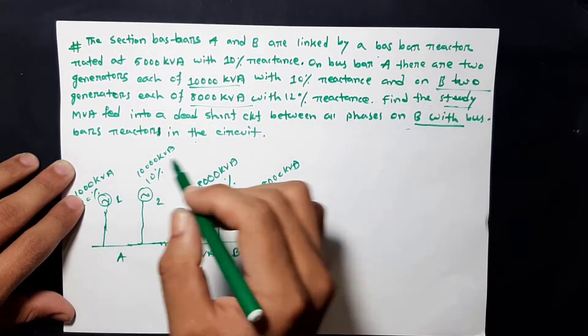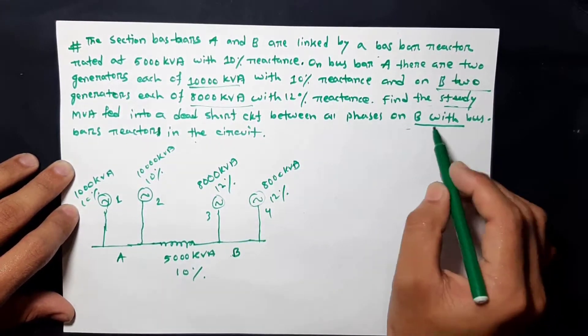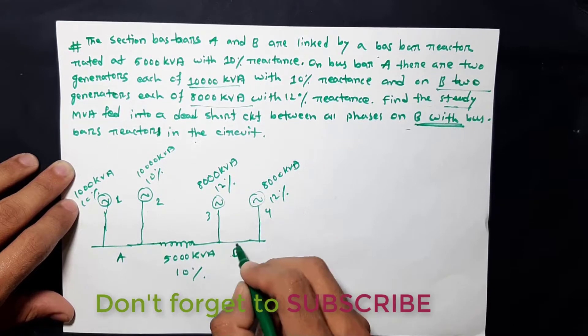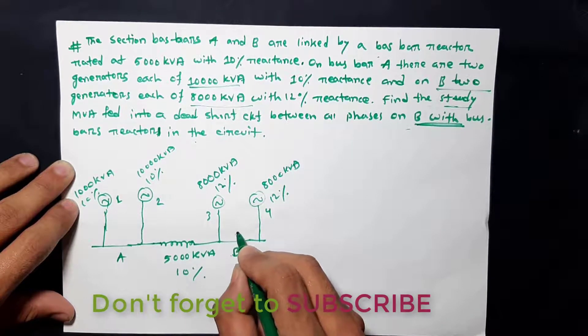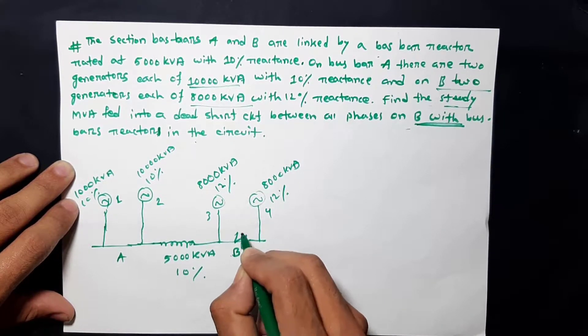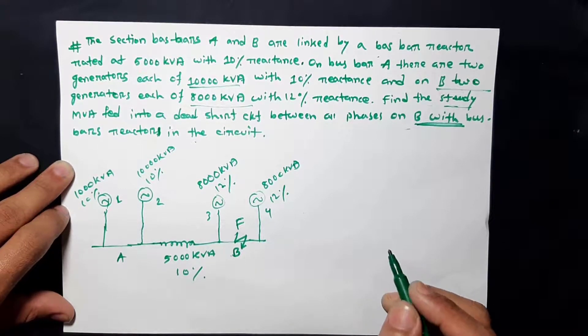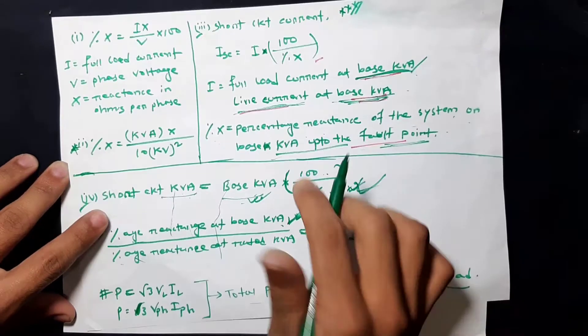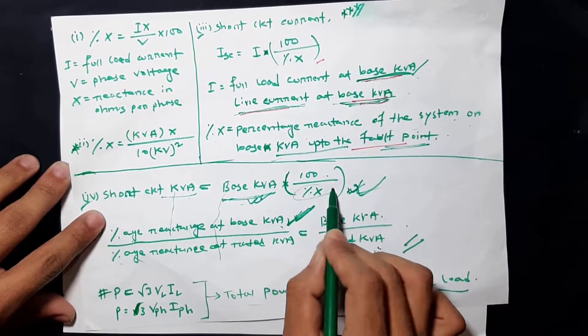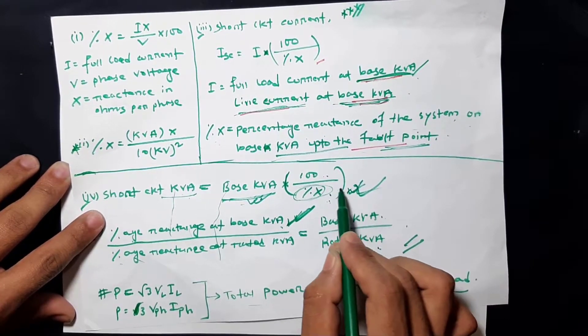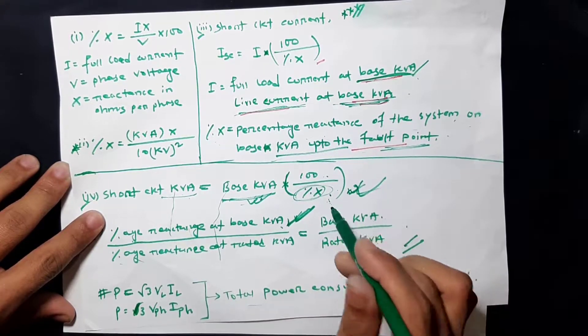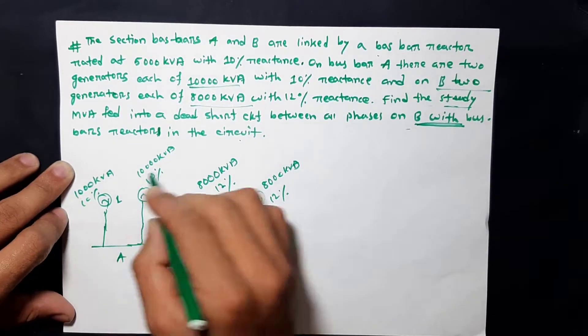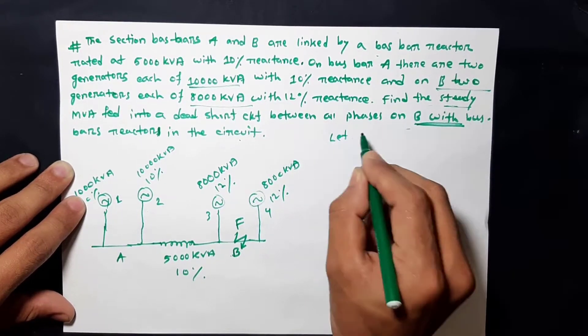We need to find the steady-state MVA for a dead short circuit between all phases on bus bar B — that means the fault is at that point. To do this, first we select the base KVA of the system, then calculate the percentage reactance of all elements referred to that base KVA up to the fault point.